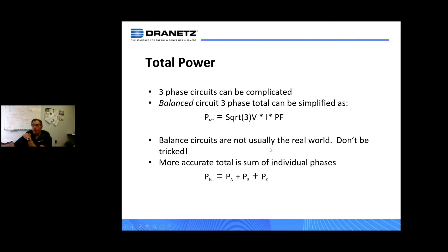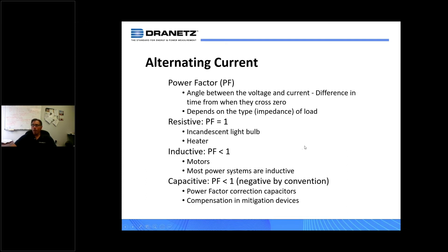Looking at the energy side, we're usually talking about three-phase circuits, although there are single-phase and split-phase applications. The important takeaway is: if you want the total power in a three-phase circuit, do what the metering does — add up each individual phase to get the total power. Balanced circuits aren't really for the real world. Make sure you're looking at each individual phase and getting the total as the sum of all individual phases.